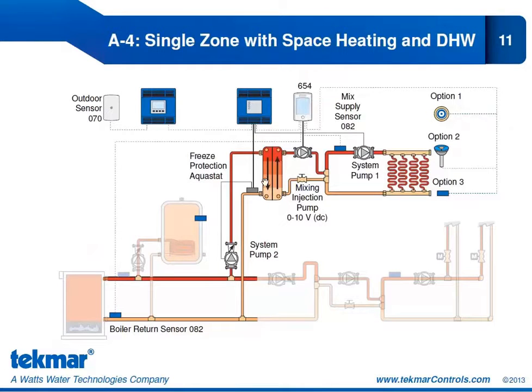You'll notice we have a freeze protection aquastat here. So in this case, we want to protect the source side of the heat exchanger, so the water side. The other side is the glycol, and so we don't have to worry about that, but we do need to worry about the water side or the source side of the heat exchanger. So by connecting that pump through a freeze protection aquastat, whenever these temperatures near freezing, we're going to turn off this pump. You'll notice there is no isolation relay for system pump 1 or for system pump 2. And that's because, as you can see here, it's not connected to the 654. The 654 has been connected to a wiring center, and the wiring center is operating that system pump. The wiring center is also operating system pump 2.